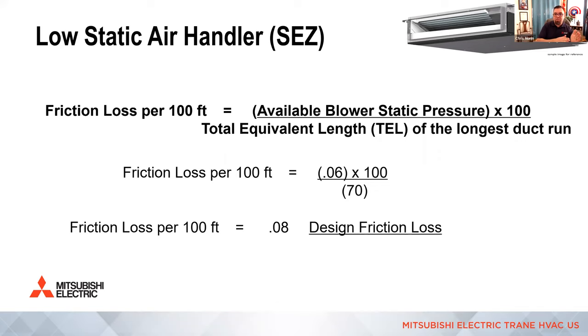If it's between 0.06 and 0.16, believe it or not, unfortunately, right in the middle is that rule of thumb that everybody uses, which we don't want anyone using anymore, at 0.1 rule of thumb. The closer to 0.1, the actual system design, the better, because we have room to go up and down when it comes to static pressure losses or poor duct design. We can turn the fan up in order to overcome that sometimes.